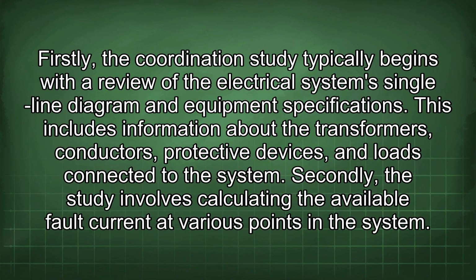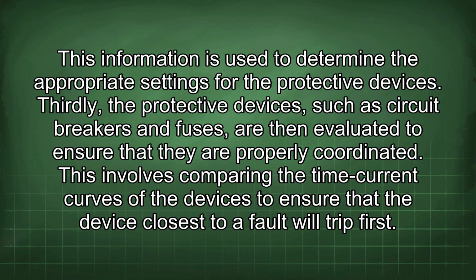Firstly, the coordination study typically begins with a review of the electrical system's single-line diagram and equipment specifications. This includes information about the transformers, conductors, protective devices, and loads connected to the system. Secondly, the study involves calculating the available fault current at various points in the system. This information is used to determine the appropriate settings for the protective devices.